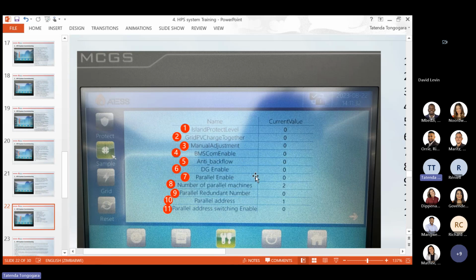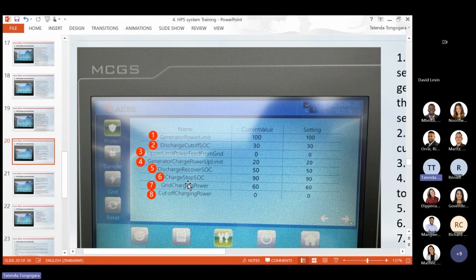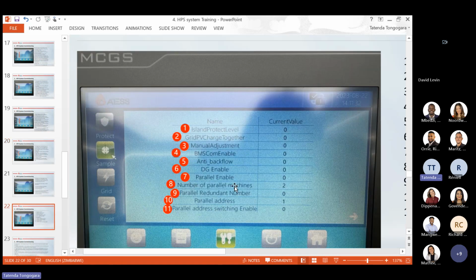Anti-backflow. If you want to export power to the grid, if you have the license to export, then you set it to 0, and then you can also set the amount of power that you want to export using upper limit feed from grid. It has been changed. There was a problem with the English that was written here, but the code has been changed now. It's upper limit to grid, that's feed to grid. So you can set it to 20 kilowatt, and then your system can only feed 20 kilowatt to the grid.